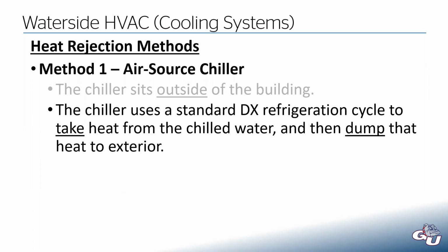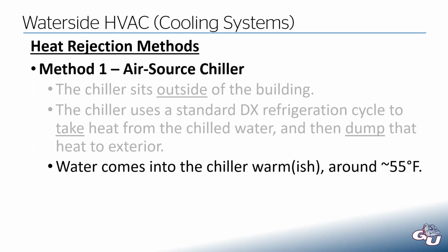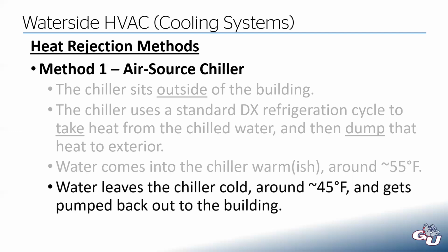So this should sound very similar to an air conditioner. We're taking heat from the water and then dumping it outside. Our water's coming into the chiller a little warm because it's absorbed heat from the building, around 55 degrees. And then we reject that to the outside, and then it'll leave the chiller, go back into the building at a colder temperature, and then just keep going through that cycle.